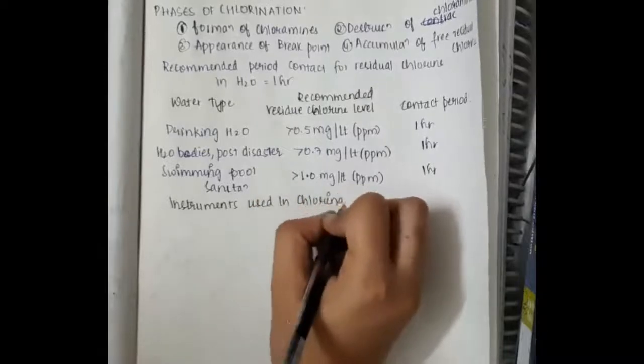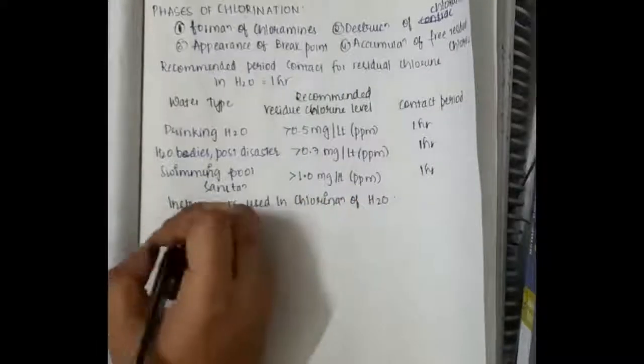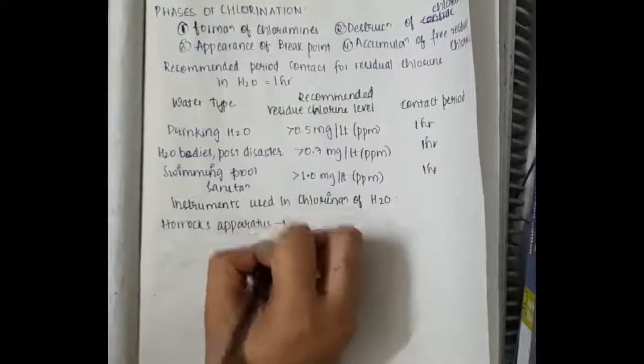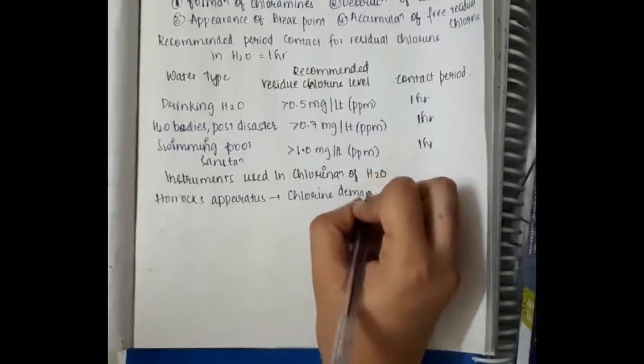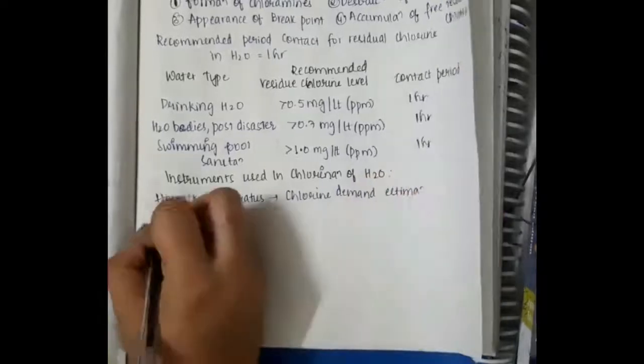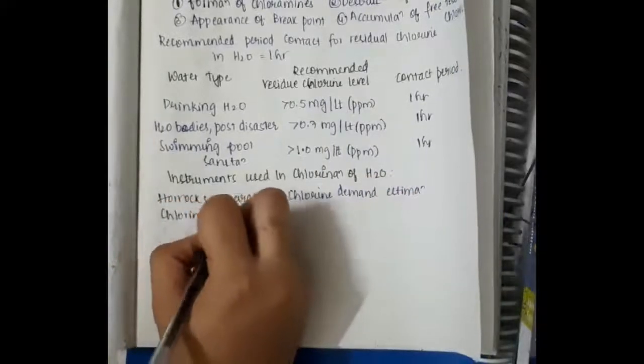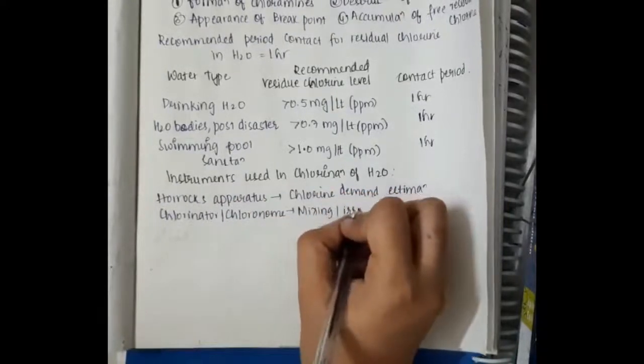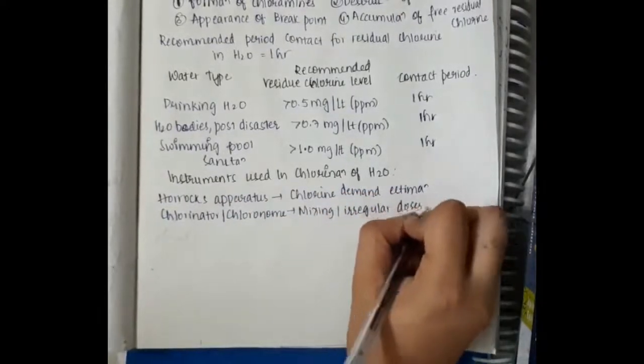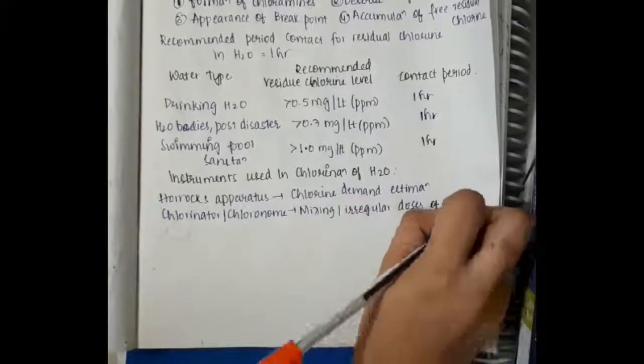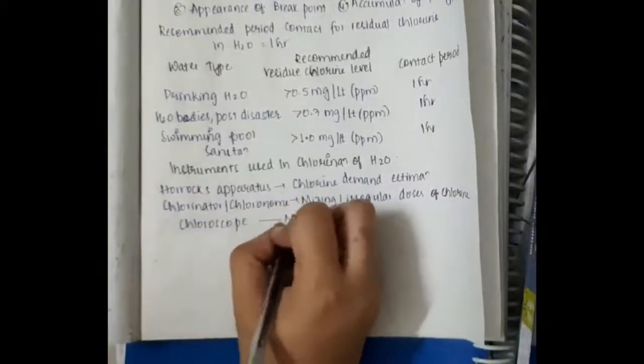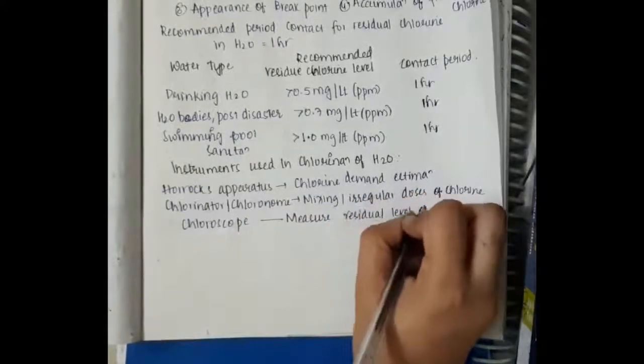The instruments used in chlorination of water are: first, the Horrocks apparatus, which is used for chlorine demand estimation; second, the chlorinator or chloronome, which is used for mixing or metering irregular doses of chlorine required for disinfection; and third, the chloroscope, which is the instrument that measures the residual level of chlorine.